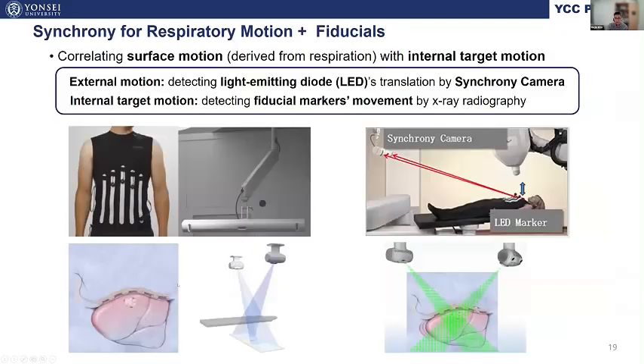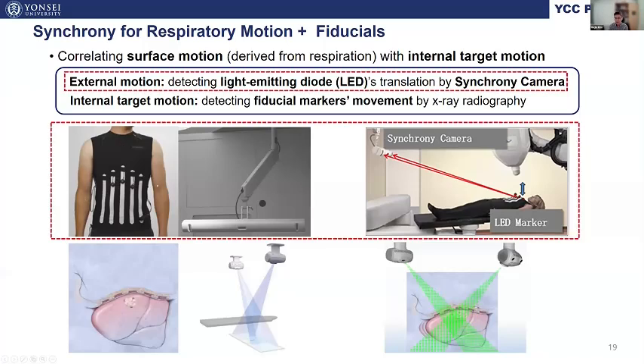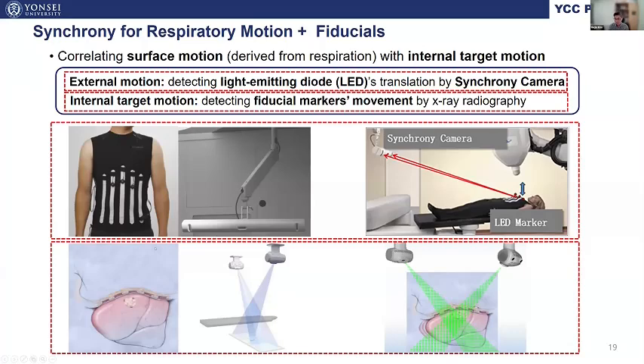Fiducial tracking can be more powerful when it is combined with a so-called synchrony camera that keeps tracking the external markers on the patient. This is known as synchrony tracking, the most representative tracking protocol of CyberKnife. This system generates a model by analyzing the correlation between the movement of the external diode markers captured by the synchrony camera and the internal motion obtained from the kV X-ray images.